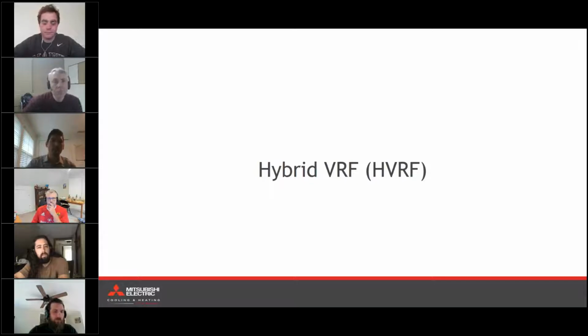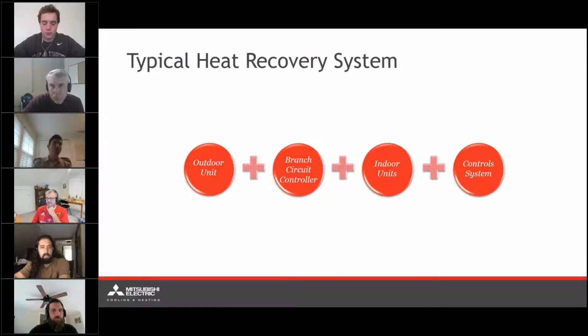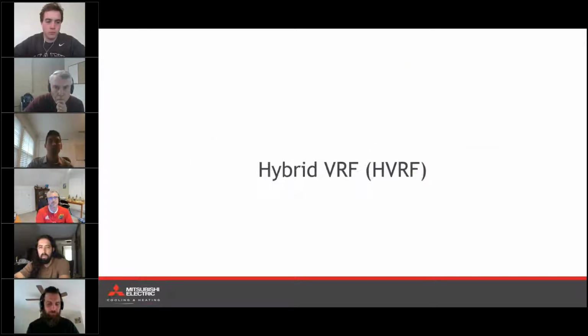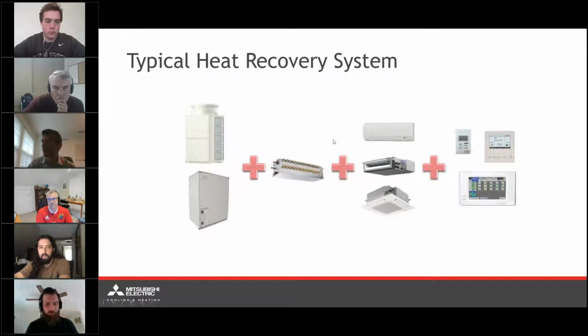But when we're talking about HVRF, we're ultimately talking about a combination of the HEX unit that we just went through and the standard heat recovery system. So just jumping back to the components that make up a heat recovery system, the thing that makes the heat recovery system capable of simultaneous heating and cooling is that branch circuit controller, that middle component that's central in the system. So again, schematically, we're talking about the branch circuit controller here in the middle. Now, the HEX units, as we talked about before, are just seen in the system as indoor units. It's just another indoor unit in the system. So what hybrid VRF does is it incorporates a HEX unit into each individual port of the branch circuit controller.